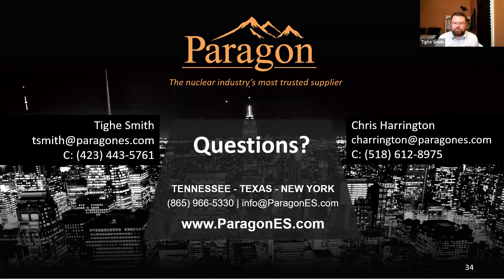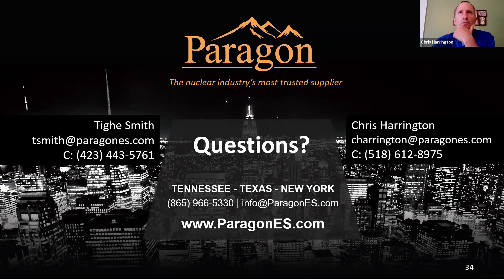A question over email: how do we screen foreign manufactured items used in repair? Most semiconductor components are made outside the United States — that's no secret. Even some surplus components are only available in overseas locations. We have a thorough receipt inspection process as well as a component vetting process to make sure it meets certain criteria before it even gets installed — screening not only for counterfeit and fraudulent parts, but also making sure the part meets all its design criteria and will function as it's supposed to. When it does get installed, it goes through a rigorous testing program, as well as burn-in and functional testing at the end. So it gets tested in several modes throughout the repair process.